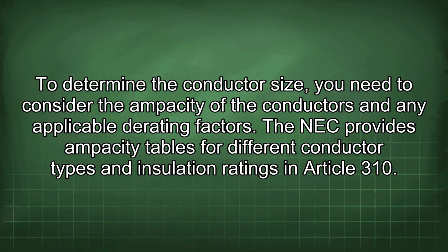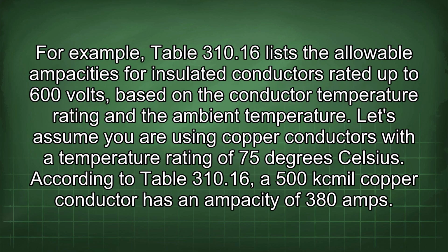The NEC provides ampacity tables for different conductor types and insulation ratings in Article 310. For example, Table 310.16 lists the allowable ampacities for insulated conductors rated up to 600 volts, based on the conductor temperature rating and the ambient temperature. Let's assume you are using copper conductors with a temperature rating of 75 degrees Celsius. According to Table 310.16, a 500 kcmil copper conductor has an ampacity of 380 amps.